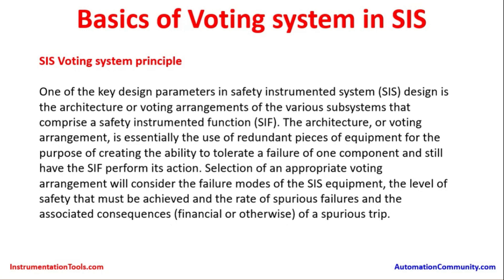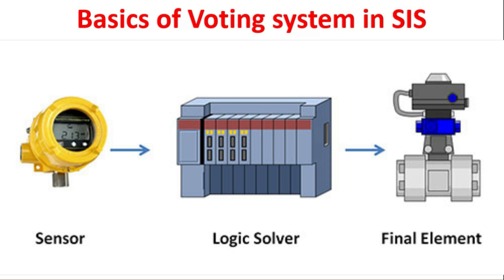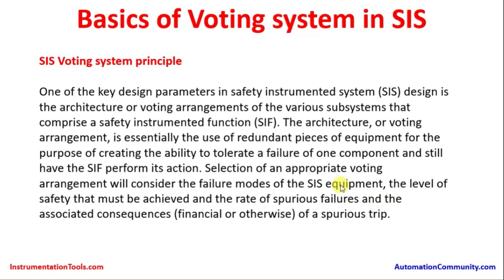This is applicable for all three main components of the safety instrumented function: the sensor, logic solver, and final control elements. When selecting an appropriate voting arrangement, we consider the failure modes of SIS equipment, the level of safety that must be achieved, and the rate of spurious failures and their associated consequences — which may be financial or potential damage to equipment.